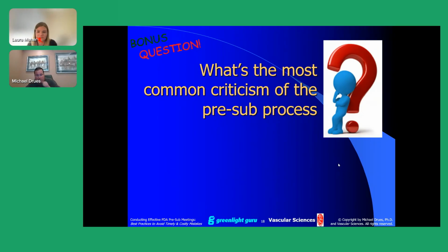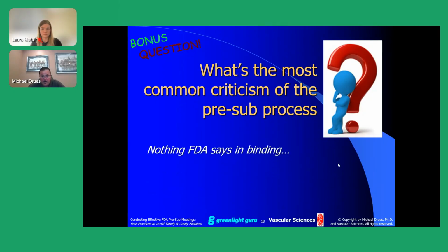So here's another question. And by the way, some of these slides you'll see there's a little bonus question thing on there, because this was not included in the agenda, but I've added a few additional things. What's the most common criticism of the pre-sub process? I've got a lot of criticisms of the pre-sub process. I pointed out some of the limitations a little bit earlier, but clearly the biggest criticism that I hear from industry all the time is that nothing FDA says is binding.